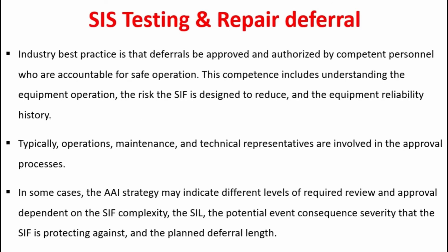SIS testing and repair deferral. Industry best practice is that deferrals be approved and authorized by competent personnel who are accountable for safe operation. This competence includes understanding the equipment operation, the risk the SIF is designed to reduce, and the equipment reliability history. These are several factors to be considered. Typically, operations, maintenance, and technical representatives are involved in the approval process.